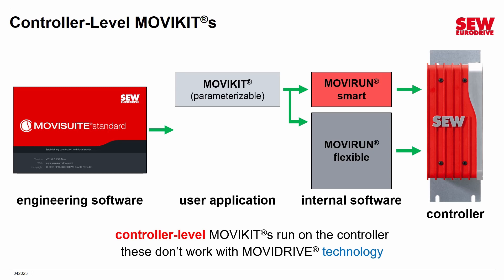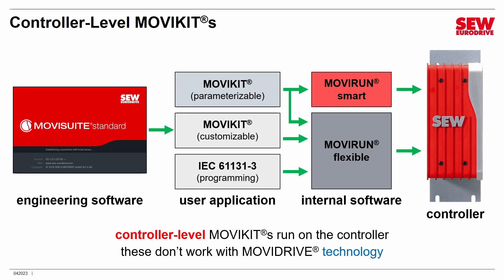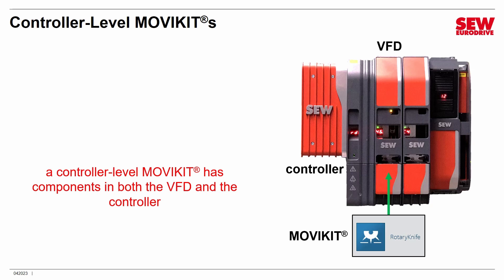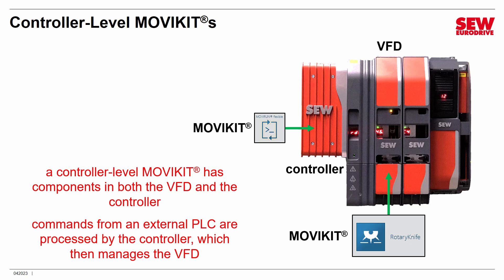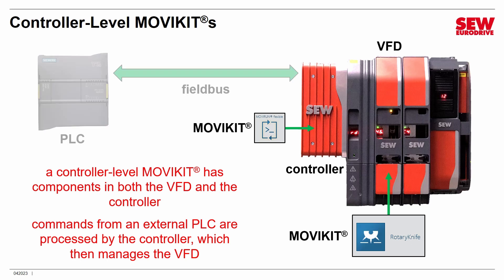Besides standard parameterizable kits, there are also customizable MOVIKIT kits and completely custom IEC 61131-3 PLC-type programming, though those are advanced topics not covered in this class. A controller level MOVIKIT has two components: one that lives in the VFD or access module and one that lives in the controller itself. Commands from an external PLC are processed by the controller, which manages the VFD — doing the heavy lifting while the PLC just sends a few basic commands.